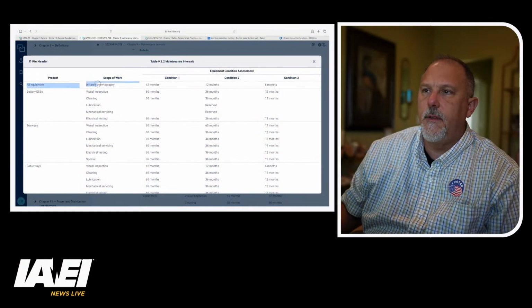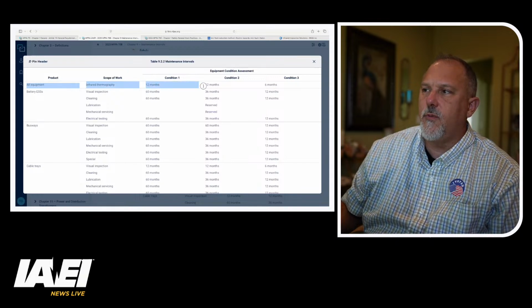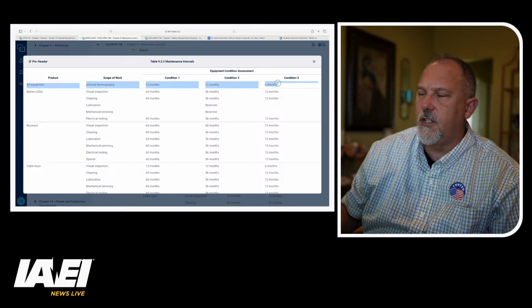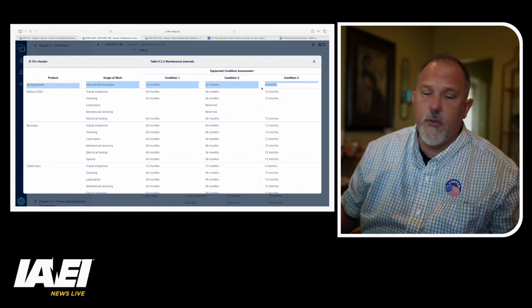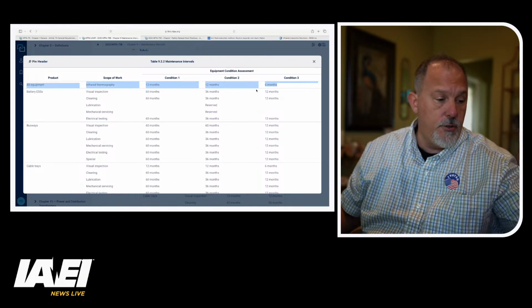I don't even have to do that. All equipment, right at the top of the list. All of the equipment, thermography: condition 1 is 12 months, condition 2 is 12 months, condition 3 is 6 months. So all electrical equipment has to have thermography. That would include transformers. So I would have to do thermography on a transformer. And if I have to take those covers off, I'm doing energized work. Unless I have those infrared, I tell you what, I'm seeing the value of IR windows more and more.